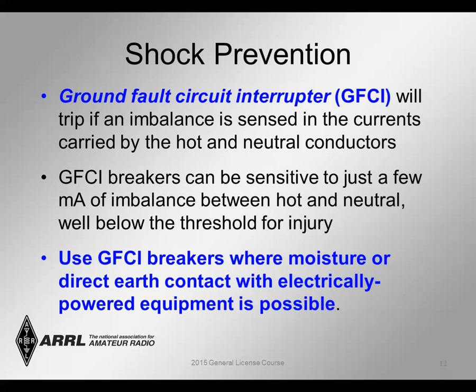And the reason for that is if you do get a little imbalance, if you look at a 120 volt circuit, the current in the black line should be equal to the current in the white line, and if it isn't, that means the current's flowing somewhere else, which is a bad condition. So then the ground fault interrupter will shut the breaker down. So if you've got moisture or direct earth contact with electrically powered equipment, it'd be a good place to use ground fault GFI breakers.